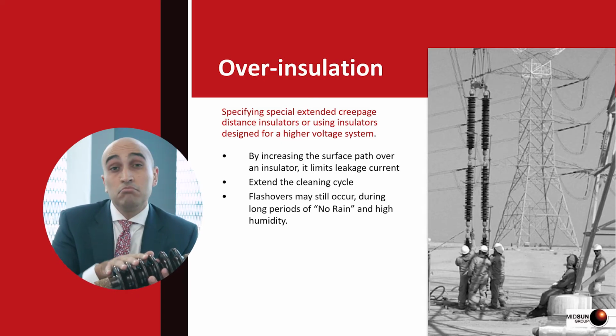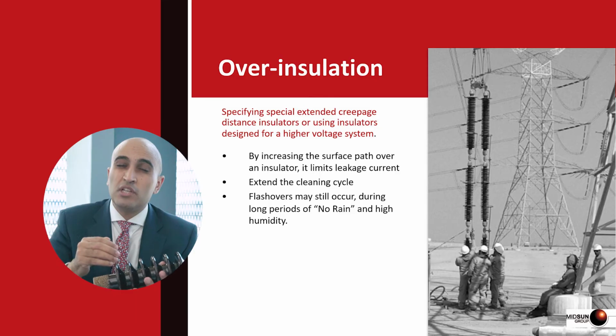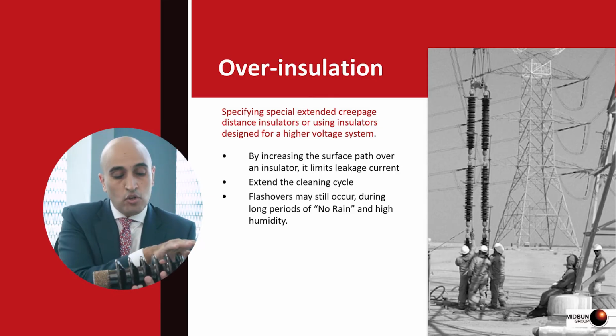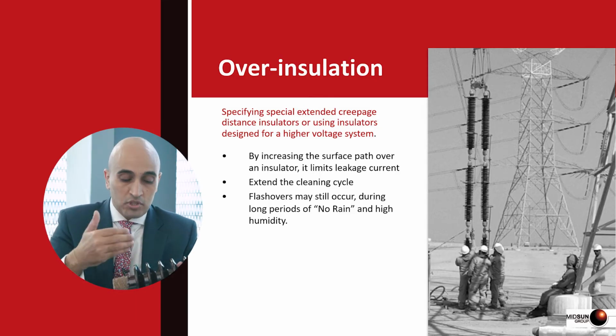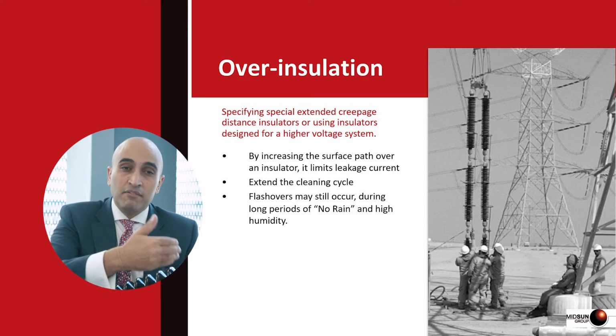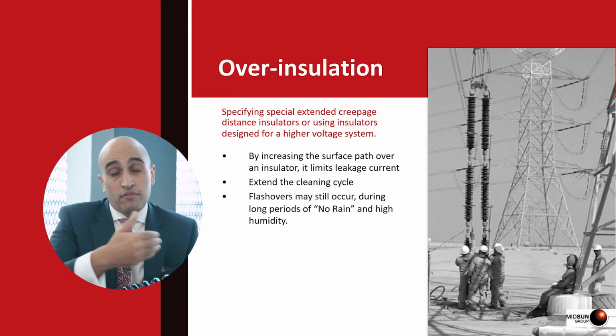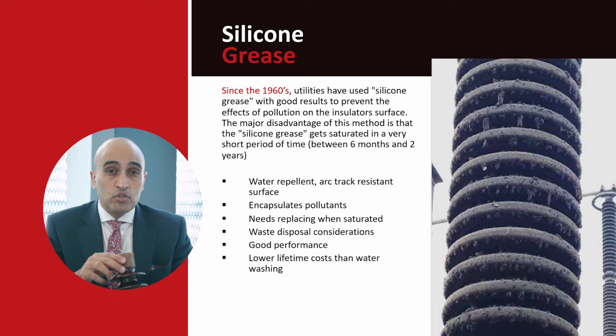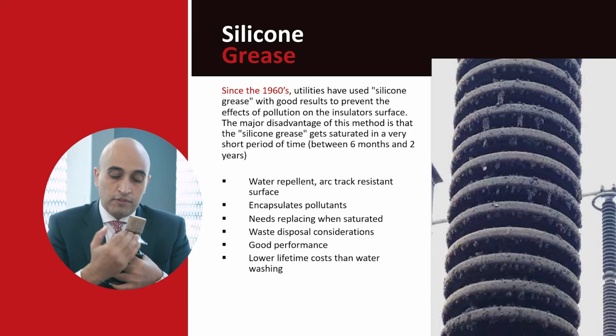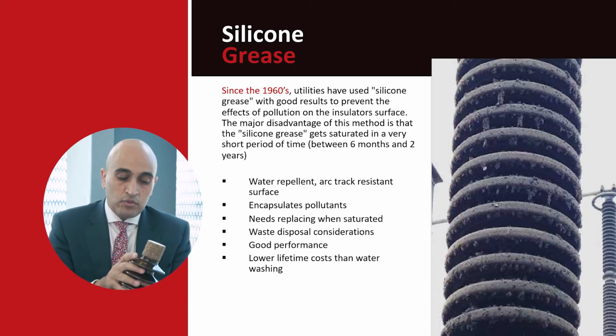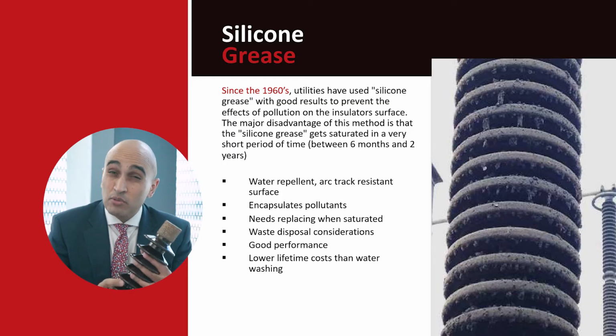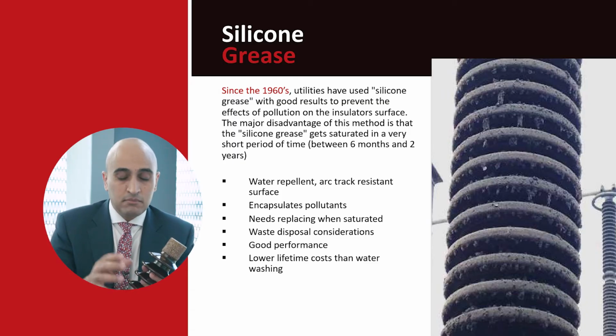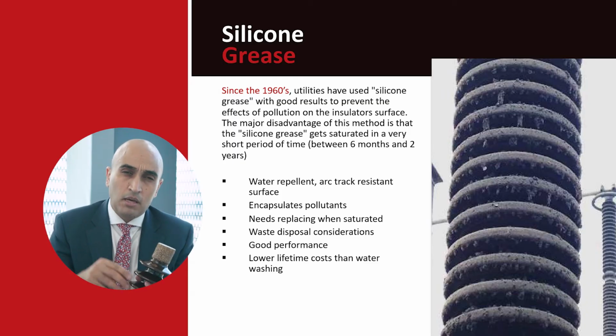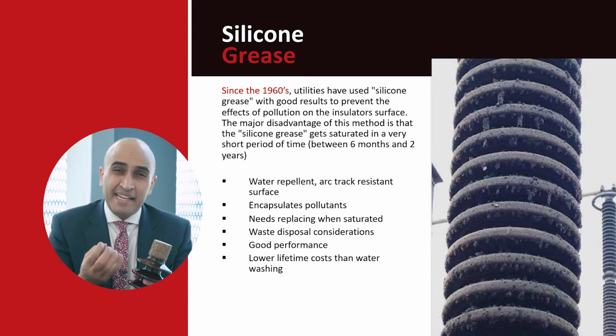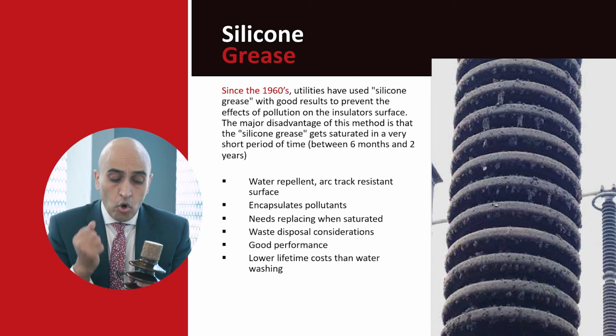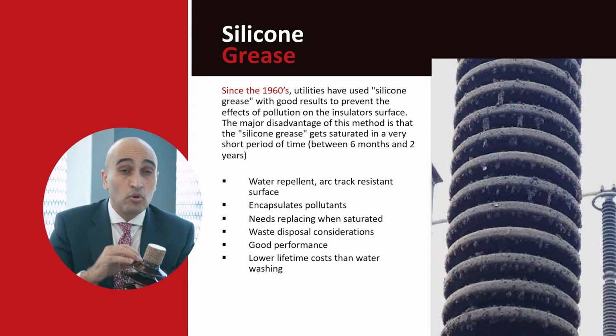This approach works. However, it also works in the short term. As soon as the full string is contaminated, we will start seeing the same effects that cause flashovers. The third approach is the modification of the surface of the insulator. Modification of the surface of the insulator could be done by using composite insulators, which have some, I would say, mechanical issues, or by using silicone grease or RTV coating.